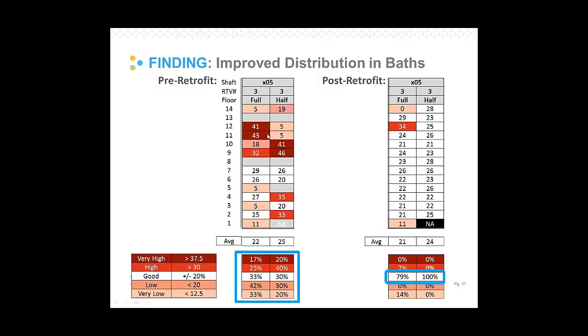Their bath shafts tended to be a little more like this. Airflow was all over the map. On the bath shafts, they were serving two back-to-back bathrooms on every floor, which is why there are two measurements. You can see some dark red, some high, some pink, which is low to no flow, and then some good flows, kind of all over the map. This is where they were having the odor and moisture issues, particularly. This is kind of where the problem was.